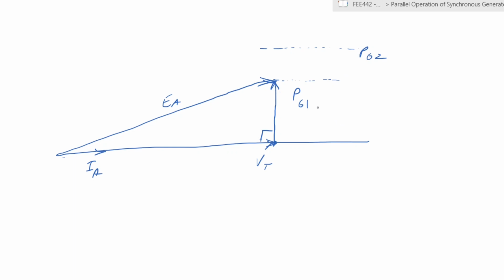You then have to change the value of the internal generated voltage. But remember here, in order to change from PG1 to PG2, we have changed your governor set point. But we are saying what happens if we change the governor set point, but we retain the voltage regulator. You change governor set point without changing voltage regulator. If you do not change the voltage regulator, what does that mean?